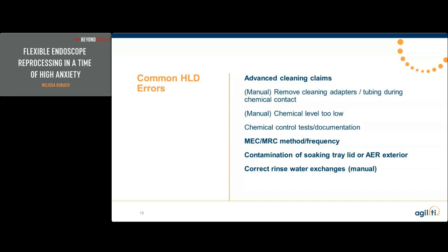And if this isn't in the manufacturer's IFU, then you may be out of compliance with your own policy. Plus, there's also some advanced cleaning claim units that will not allow you to reprocess under advanced claims with an exposed elevator wire. So always make sure that you really understand those claims, have something in writing on those claims.